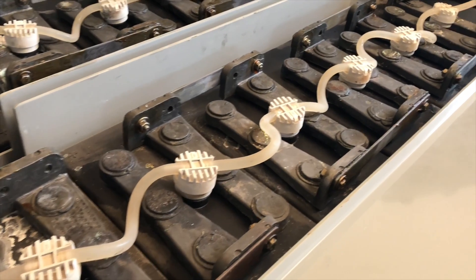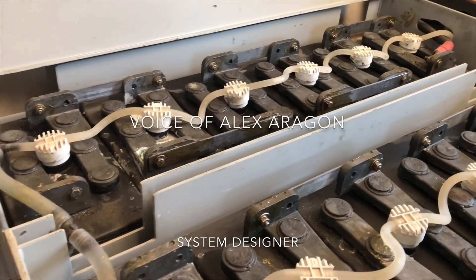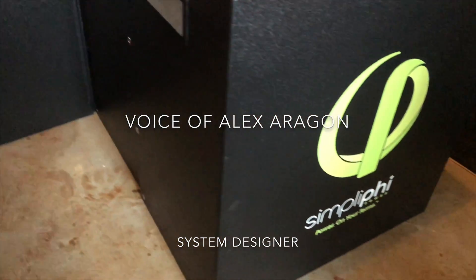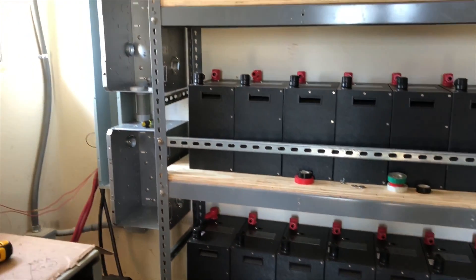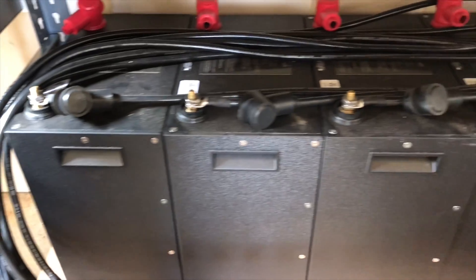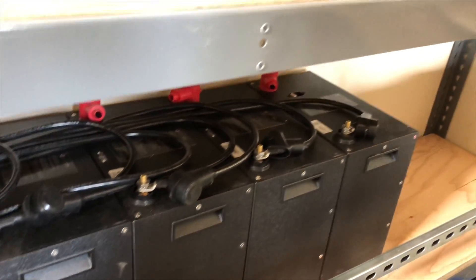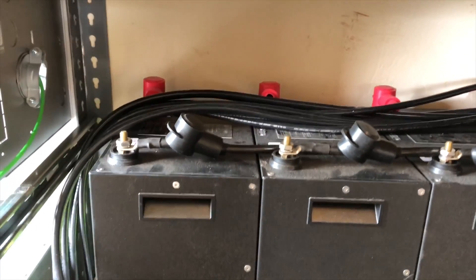The old lead acid batteries had 144 kilowatt hours of storage in them. Our new SimpliPhi batteries have about 81 kilowatt hours of total rated capacity. But with lead acid, you only want to use about 35% — the top 35% of the power on a daily basis — otherwise you start to decrease their longevity. So if we were to use 35% of the capacity on a daily basis, that would be 50 kilowatt hours of storage for the two banks we have here.